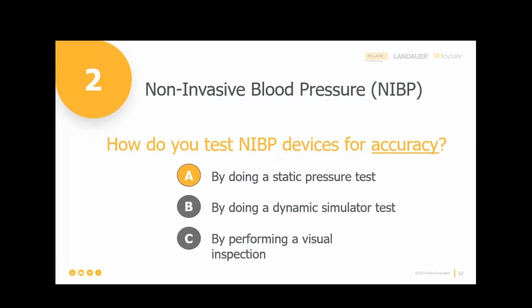And then step by step, it comes down stepwise until we see what is the peak pulsatile pressure in the cuff. And that's called the mean arterial pressure. And then at that point, there's a calculation that happens, either based on calculus, point slope, a series of point slopes, or a statistical analysis of the other pressures as we deflate the cuff. The problem is, what is the percentage left or right of mean arterial?